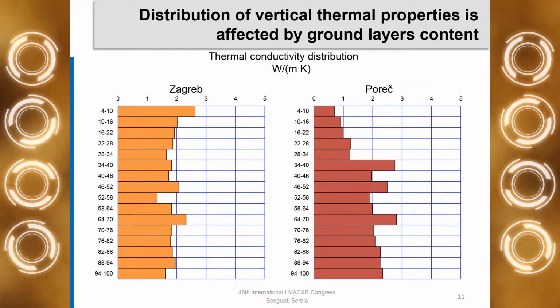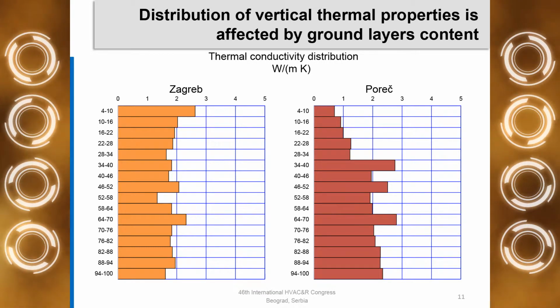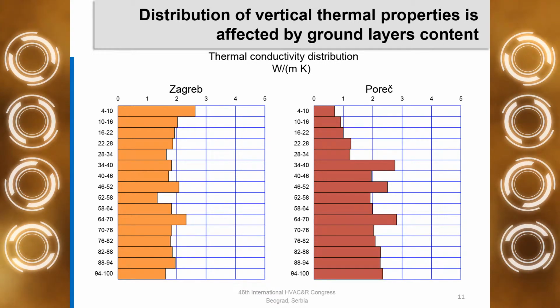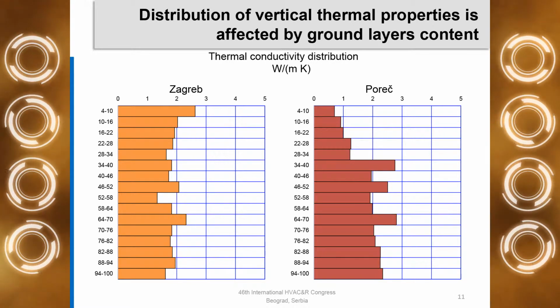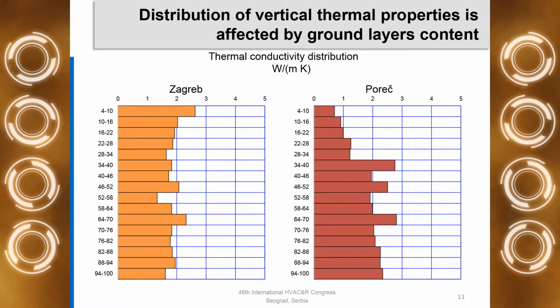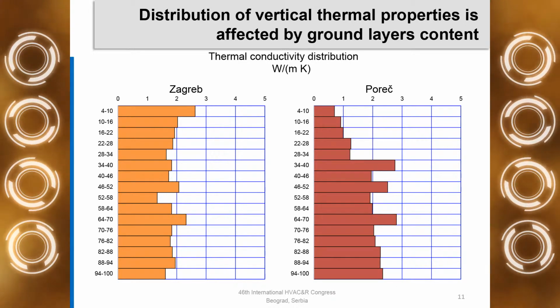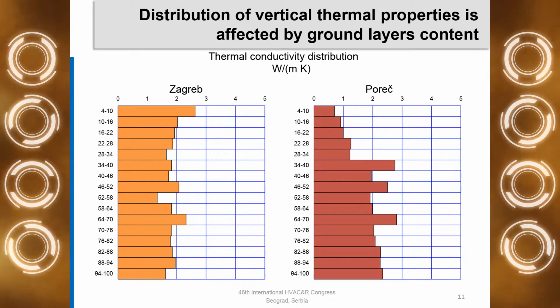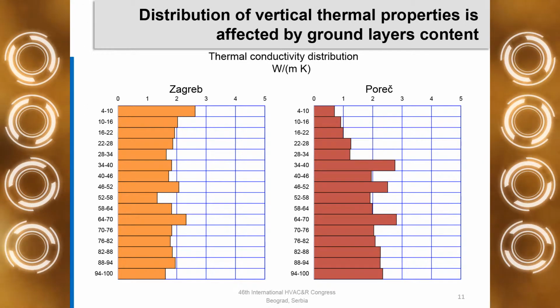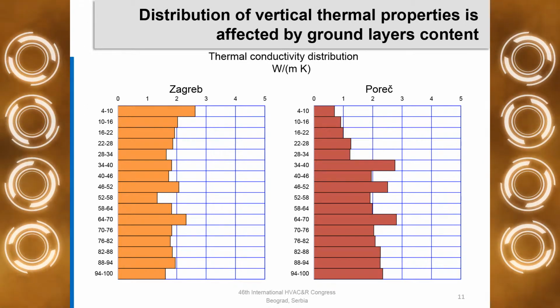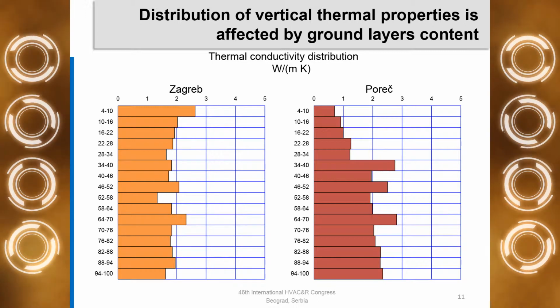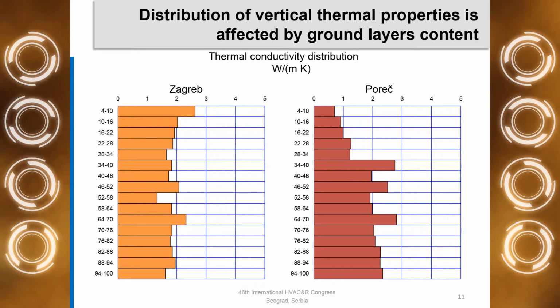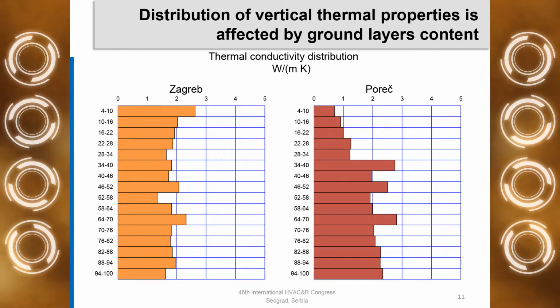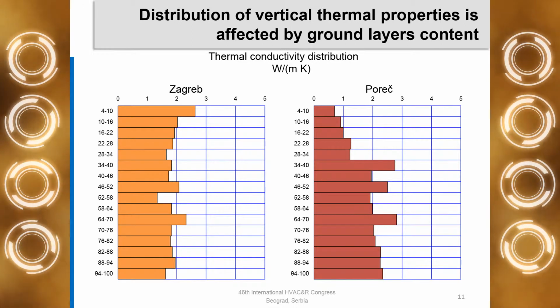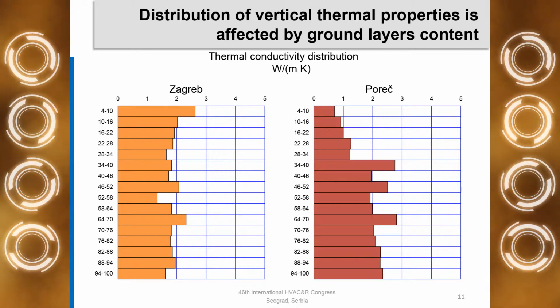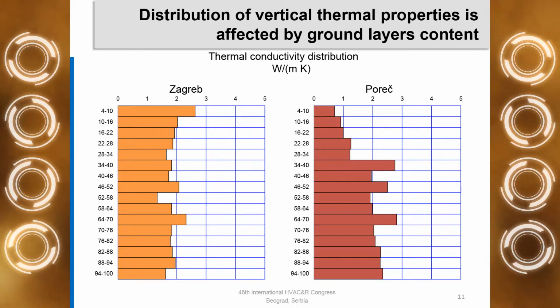By using the data obtained in the first 2 stages of the thermal response test, we are able to determine the vertical distribution of thermal properties. Depending on the ground layer's content, the thermal properties can vary more or less along the depth of the borehole heat exchanger. Here we have two locations. One is Zagreb, the capital city in the central part of Croatia. Another one is Poreč, located in the western part of Croatia, facing Italy, basically on the Adriatic coast. We can see also that the variation of thermal properties along the depth can be significantly different based on the layer content.